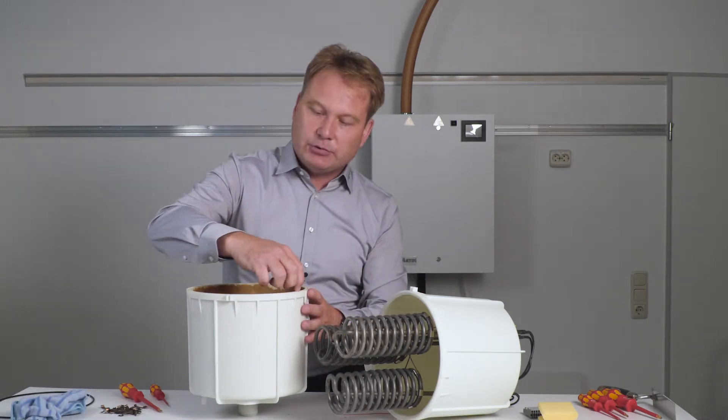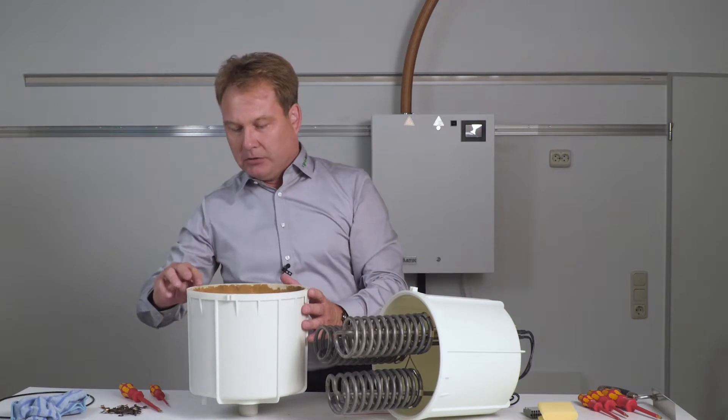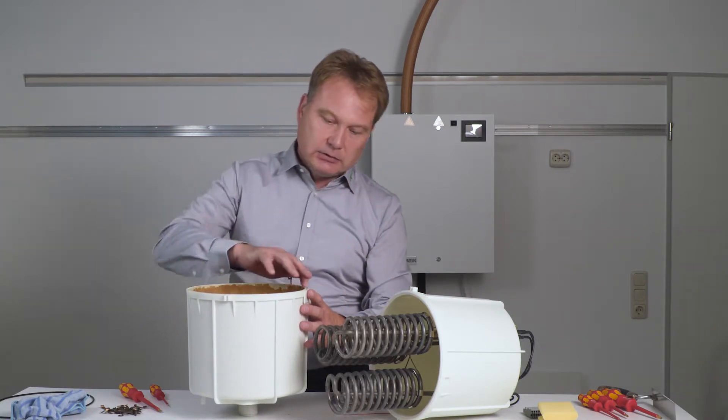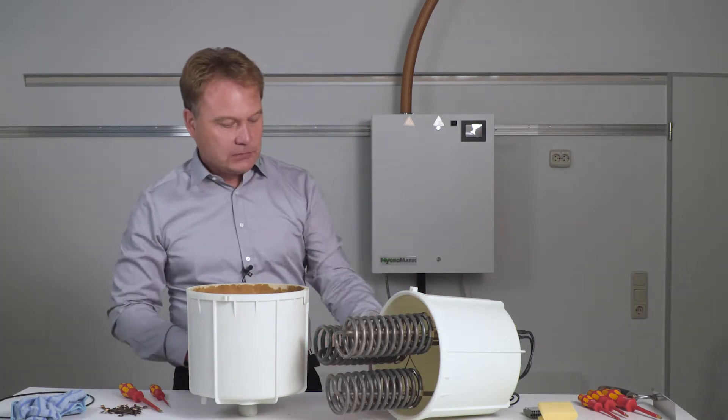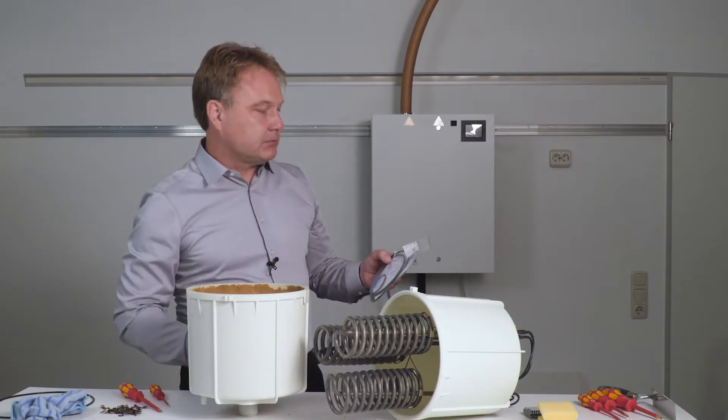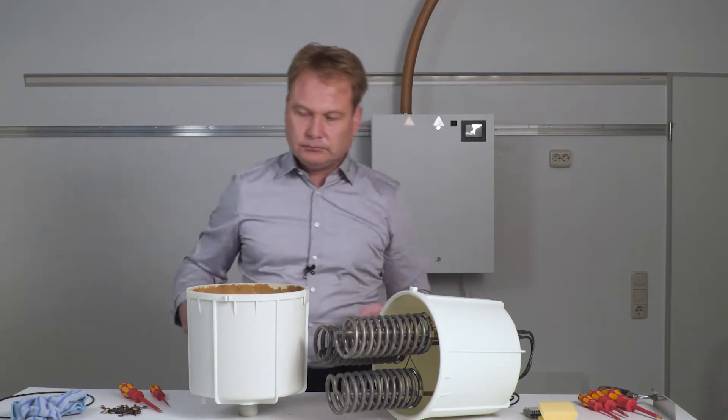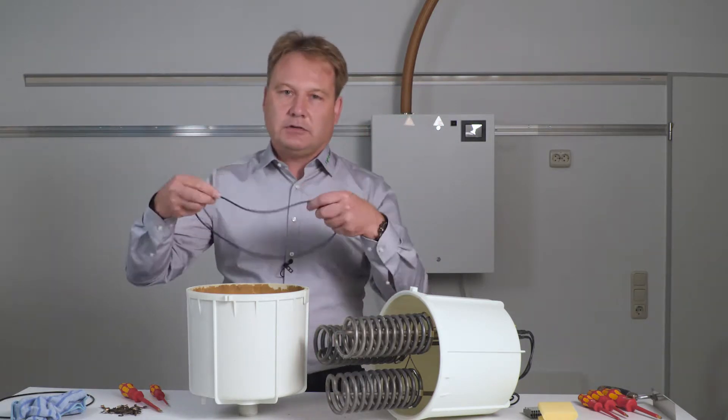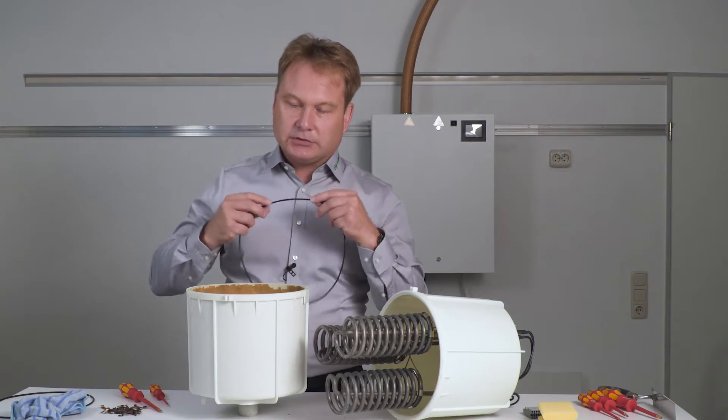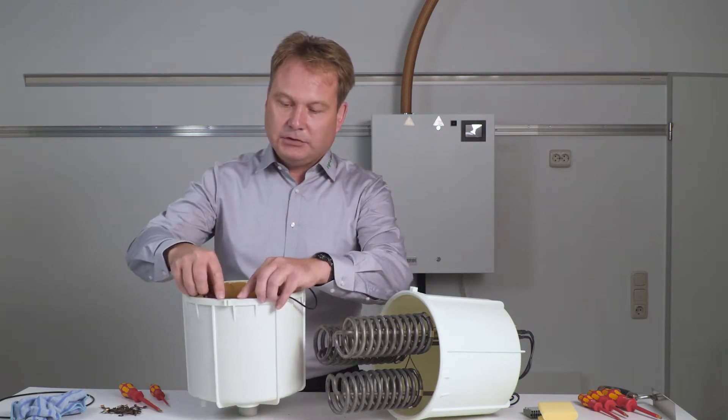And check if possible chipping is present, whether it can really close tightly. That is the case. I take a new O-ring from my O-ring set and put it on the lower half of the cylinder in the groove.